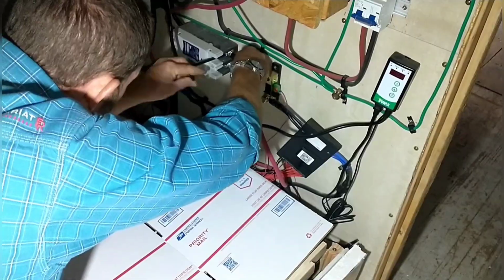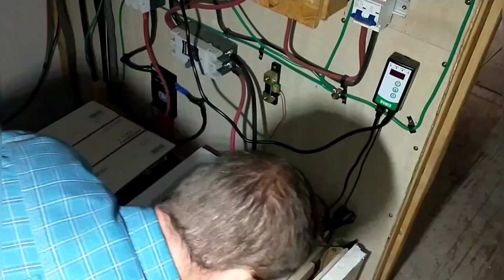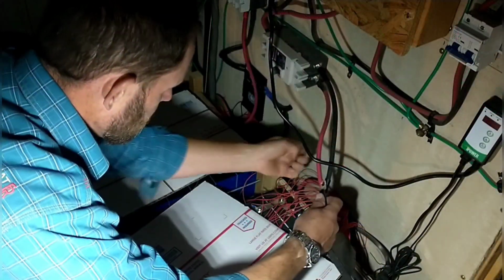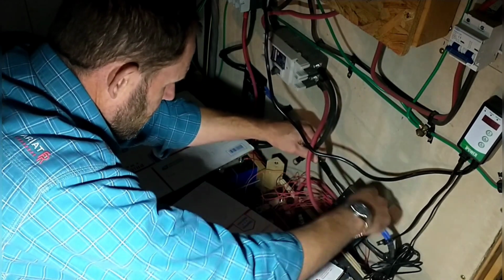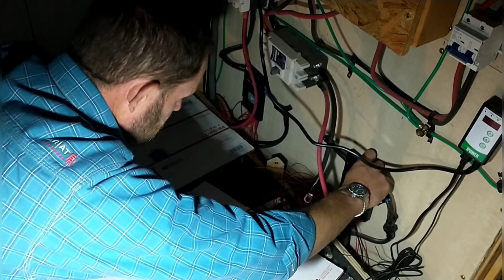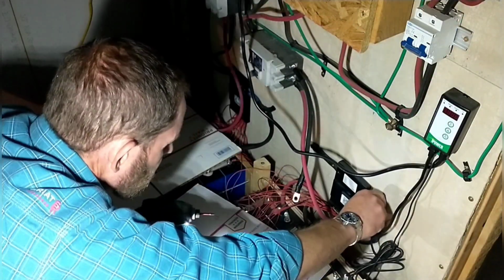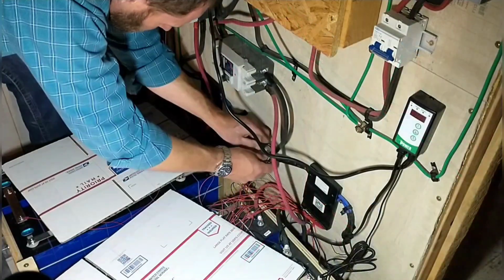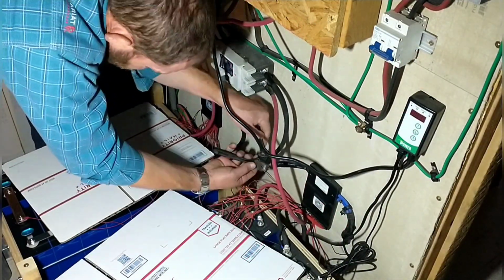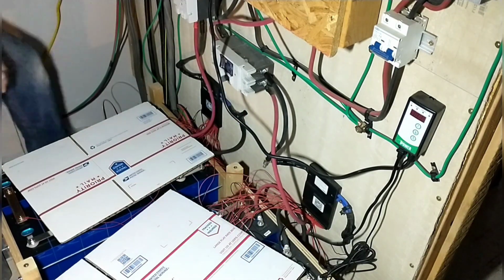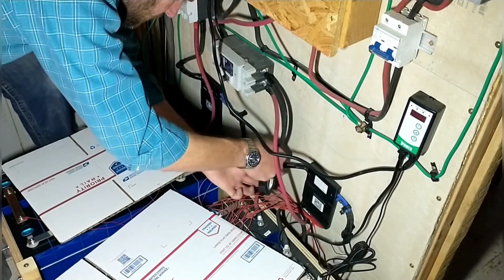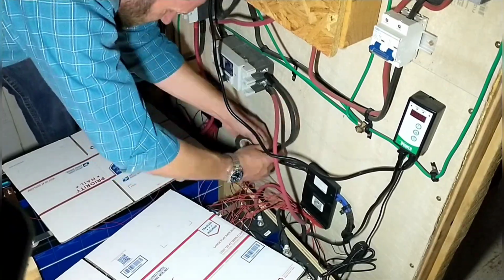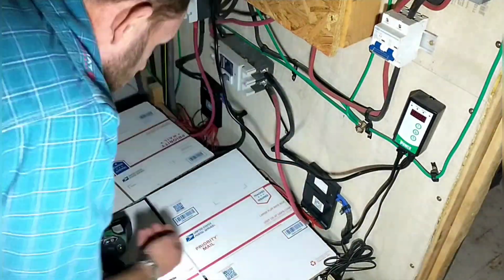While the system was down, I wanted to make one slight modification to the existing older battery: remove the Victron shunt. We installed it a bit after starting the system originally, but didn't find it very useful, so I'm removing it and connecting the BMS directly to the bus bar through the breaker. The Victron shunt worked fine, but we didn't need it since we got basically the same information from the BMS, and it also needed to be reset weekly or it got out of sync, so we removed it.